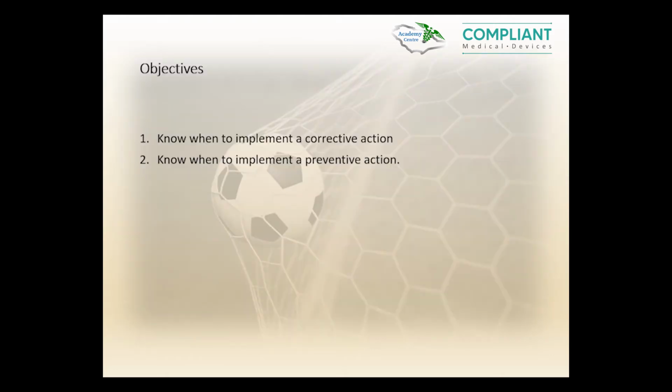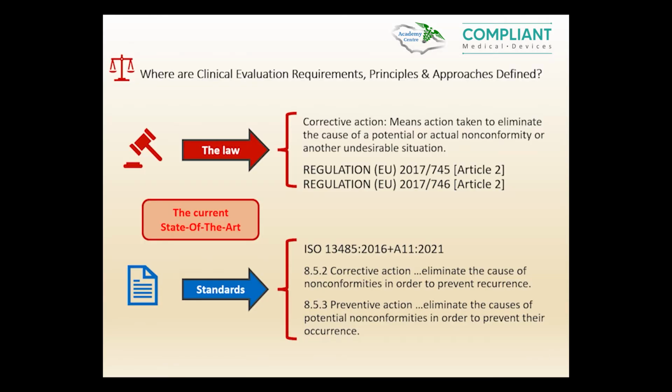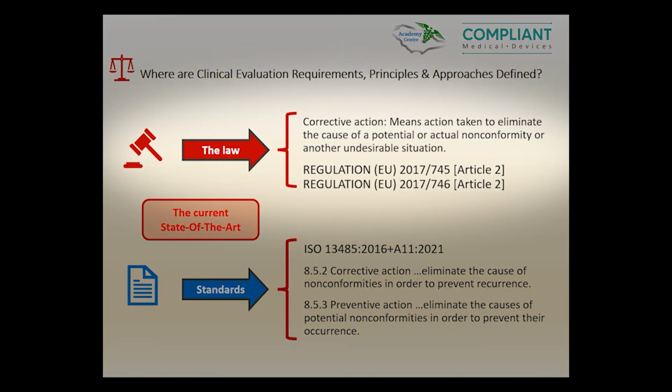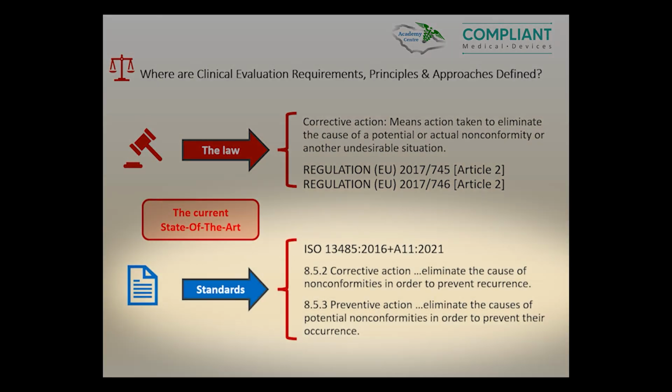So we would look at when to implement a corrective action and when to implement a preventive action. Where are the requirements defined? In terms of the law, the MDR and the IVDR define corrective action in Article 2. And the standard 13485 describes corrective and preventive action in clauses 8.5.2 and 8.5.3.